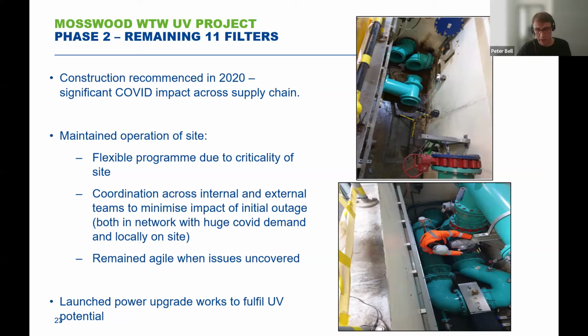So what we had to do is line up that piece of work for a good 3-4 days prior, slowly changing the filter wash sequencing. Not so much that it impacted the site, but enough that we built up a 24-hour slot to get in there, do the pipe work, remake the pipe work, and then allow the filter washing sequence to continue. Just to give some context, if we weren't to wash the filters after the running period, which is around 48 to 60 hours, depending on what the water quality profiles are like at the time, you then start to see turbidity breakthrough or loss of flow through the filter. So you would start to impact the site water qualities and quantity.